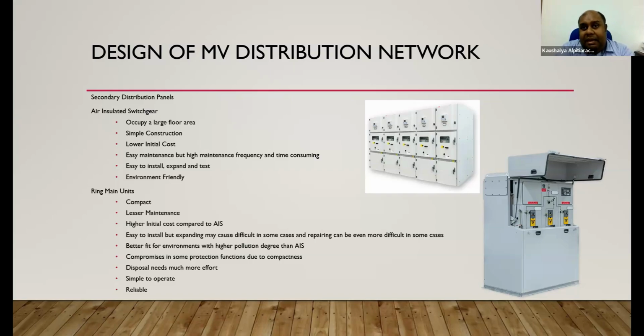Because if it keeps on reducing the gas pressure, things are going to be very bad, because air could enter after some level, and that will compromise the quenching and insulation inside the chamber, which will lead to a very catastrophic failure.